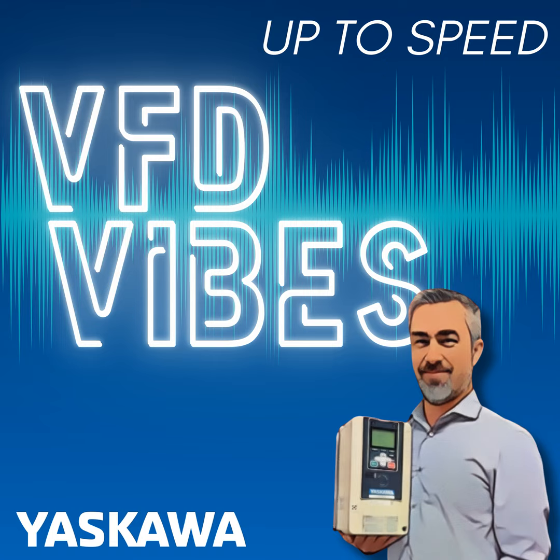I think that's one of the coolest pieces about that software is once you have everything entered on your side of that point of common coupling, you can quickly click through the different options and see instantly how they change the harmonic output. You can start with a standard 6-pulse. You can throw on a couple of filters. You can throw on a matrix, low harmonic industrial drive, a U1000. It's really neat to be able to click through and see the effects. So if you have a certain limit you're aiming for, you can look to see what's the most cost-efficient way to get there. That's correct.